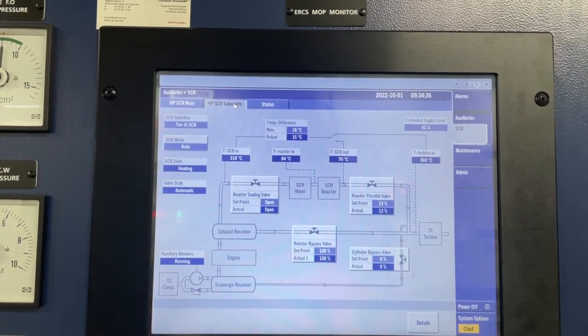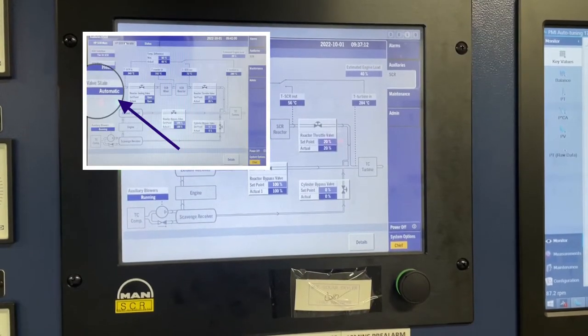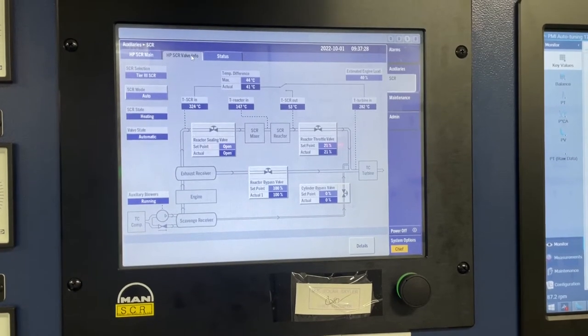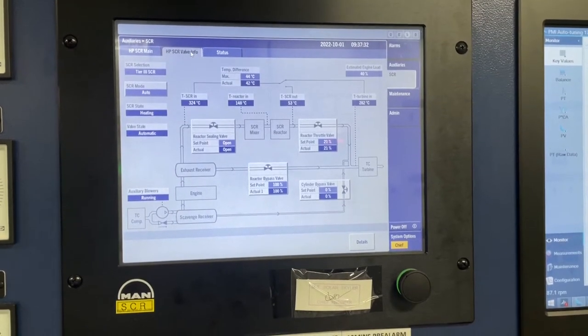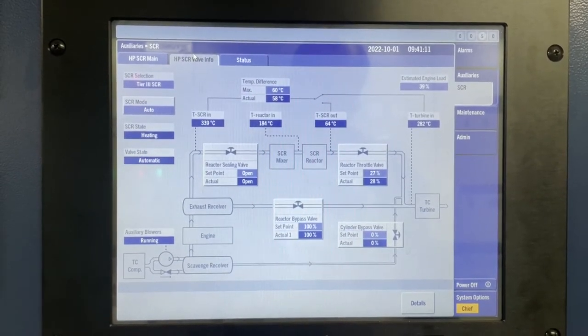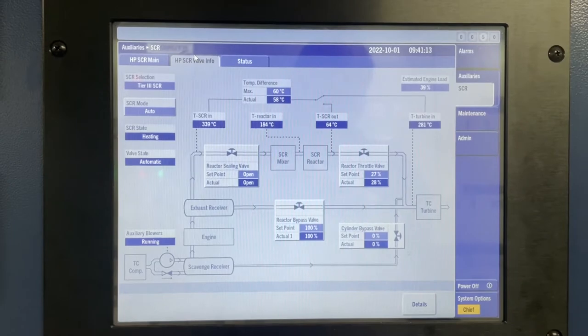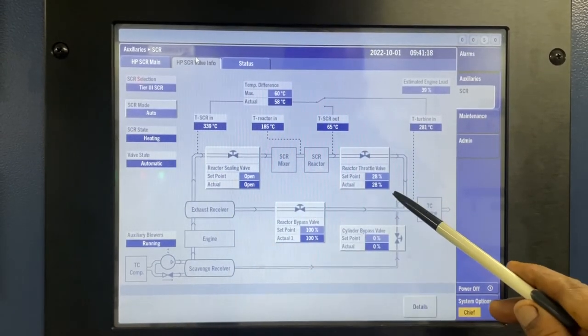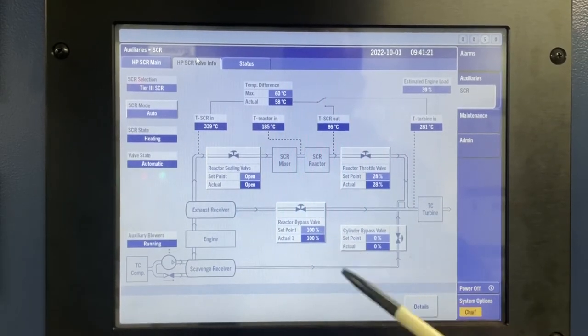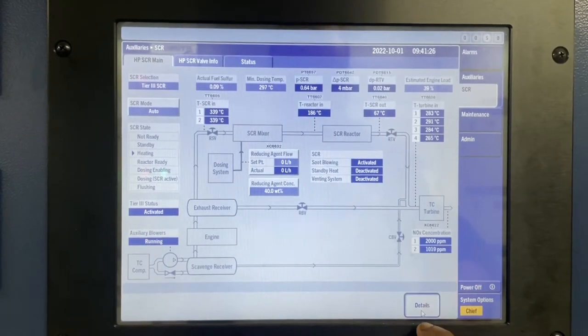The SCR valve state will change to automatic, and heating of the SCR reactor continues by slowly regulating the RTV. Only RTV will regulate to open first. After the RTV is fully open, the RBV will start to close.